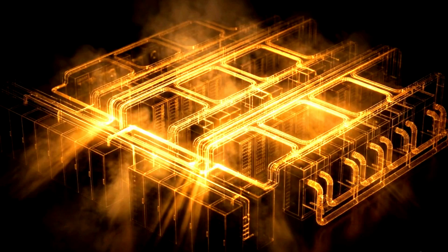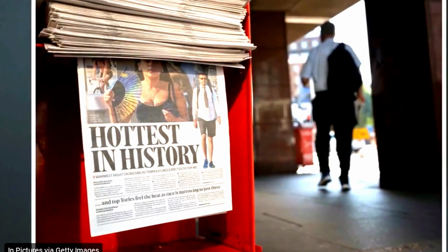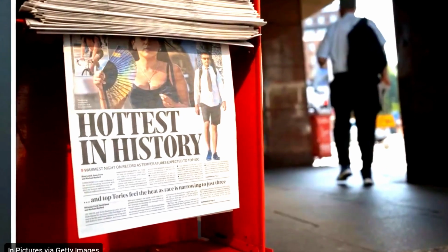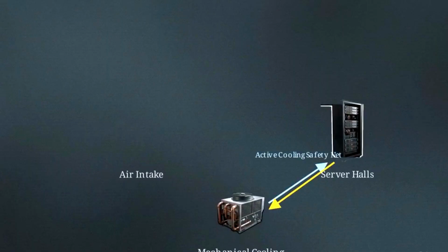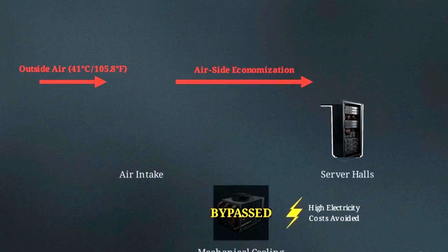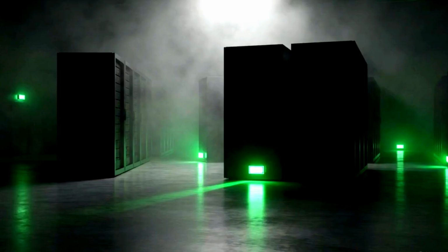Engineering principles define these facilities as energy conversion buildings. Electricity goes in, computing work is performed, and nearly all of that energy is expelled as heat. But the operators ignored the environmental data. Despite a forecast of 41 degrees Celsius, they opted for green airside economization, pulling outside air into the facility to avoid the high electricity costs of mechanical chillers. Prioritizing cost savings over the physical cooling requirements of the hardware removed the facility's thermal safety margin. The disaster was a design choice.